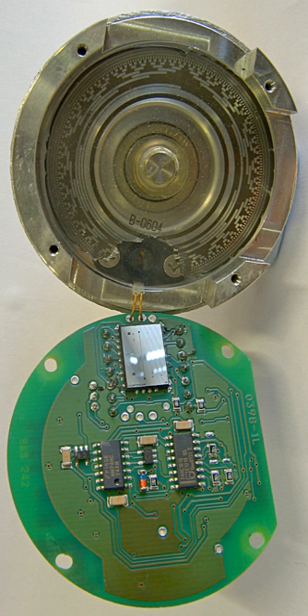Topic: See also. Analog devices that perform a similar function include the synchro, the resolver, the rotary variable differential transformer (RVDT), and the rotary potentiometer. A linear encoder is similar to a rotary encoder, but measures position in a straight line, rather than rotation. Linear encoders often use incremental encoding and are used in many machine tools.